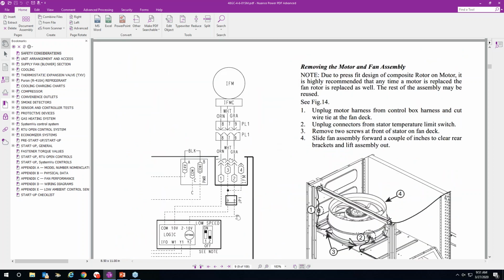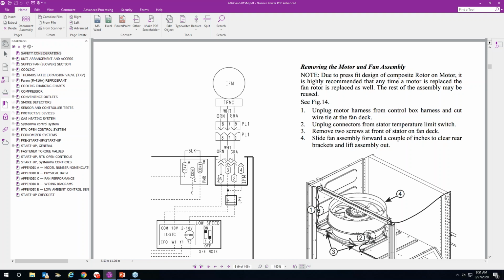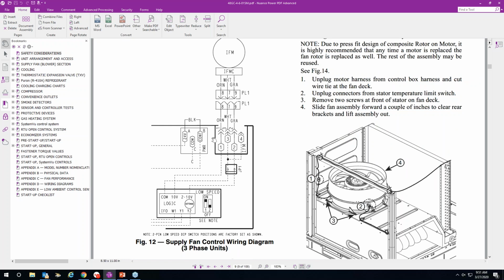But basically you can see here that you've got your 10 volts coming in on the orange lead from the fan motor. So that fan motor is going to send out 10 volts DC down the orange lead right into the board, okay? And you can pick up this reading right off the leg of that Molex connection. It's open enough to get a meter probe on there, and then you can either go to chassis ground or you can go to one of the other DC voltage taps on there that you typically plug into to set things up, okay? So you should always have from the motor into the board 10 volts DC here.